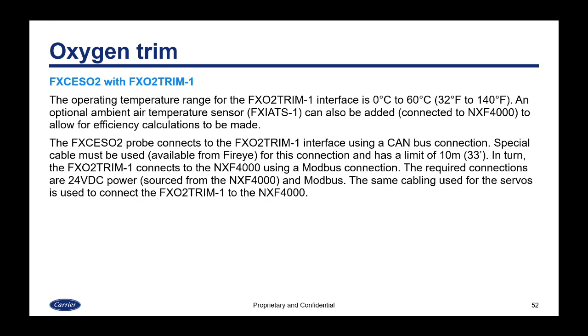The FXCESO2 probe connects to the FXO2TRIM-1 interface using a CAN bus connection. Special cable must be used for this connection, and it'll have a limit of 33 feet. In turn, then the FXO2TRIM connects to the NXF4000 using a Modbus connection, same as the NXCES02. The required connections are 24 volt DC power, which comes from the NXF4000 as well as Modbus.